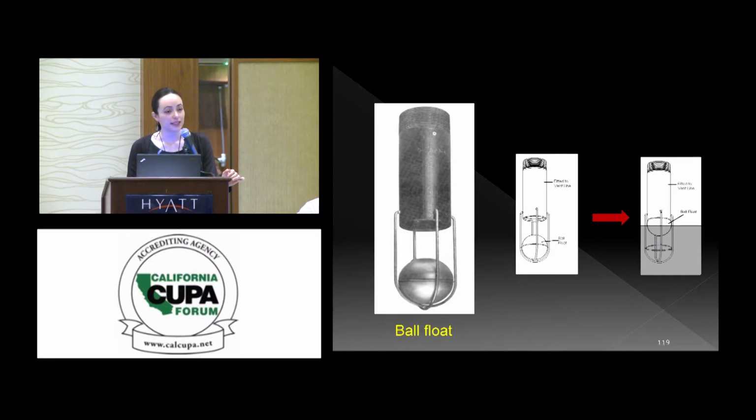Usually that would be the one that technicians actually pull out a measuring tape and measure the probe, maybe relying on the tank charts, which would say that 90% of that tank is going to be reached at 76 inches, for example. So they measure that length of the probe and put that float exactly at 76 inches, and that alarm has to go off because it's pretending that the tank is now full at 90%.